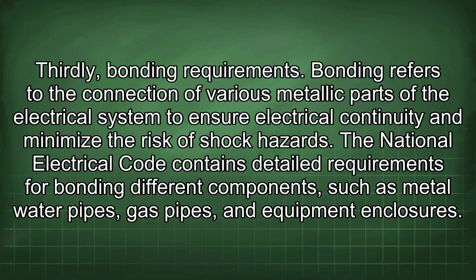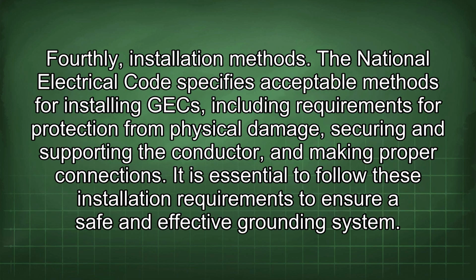Thirdly, bonding requirements. Bonding refers to the connection of various metallic parts of the electrical system to ensure electrical continuity and minimize the risk of shock hazards. The National Electrical Code contains detailed requirements for bonding different components such as metal water pipes, gas pipes, and equipment enclosures. Fourthly, installation methods. The National Electrical Code specifies acceptable methods for installing GEC, including requirements for protection from physical damage, securing and supporting the conductor, and making proper connections. It is essential to follow these installation requirements to ensure a safe and effective grounding system.